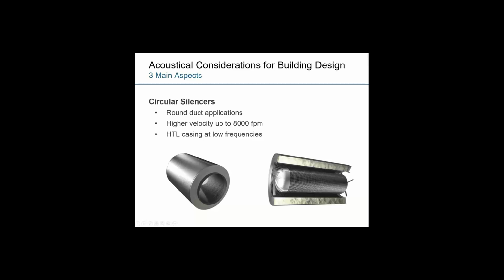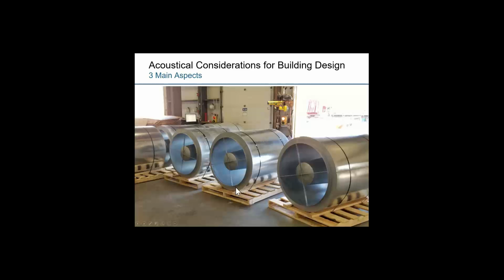Circular silencers or round duct silencers, very similar in design and intention, where sound energy would be passing through the silencer and absorbed in that outer casing acoustic media. Typically, these silencers have perforated metal on the interior, as you can see in the rendering here, and the sound energy is absorbed into that acoustic media behind the perforated metal. A couple other examples in a practical sort of picture, and you can see available in a wide variety of sizes and diameters to suit the needs of whatever application is necessary.